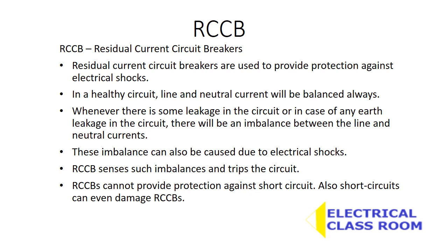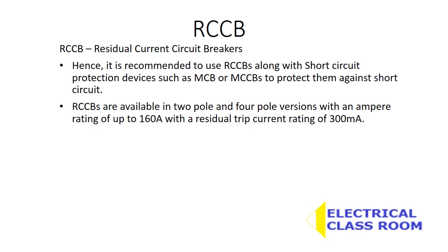The residual current circuit breaker senses such imbalances and trips the circuit. However, residual current circuit breakers cannot provide protection against short circuit, and short circuits can even damage RCCBs. Hence, it is recommended to use residual current circuit breakers along with short circuit protection devices such as MCBs or MCCBs to protect them against short circuit.